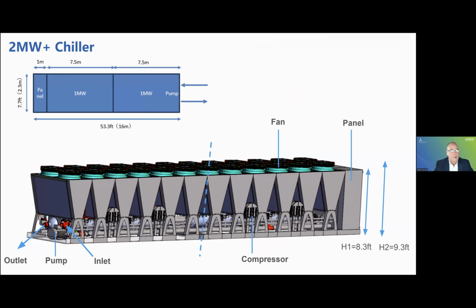Here's a look at the footprint of our 2 megawatt chiller. As you can see, as I mentioned, it's 53 feet in length, 4 compressors, 2 pumps, 7.5 feet wide by 9.3 feet high with the fans, a little bit smaller without the fans. We've designed this specifically so we can put it on a 53-foot long truck, which means a couple of things. You don't need a special route, or escort services to get the unit to the site. And secondly, once it's on site, the rigging of it is a lot easier with one solid piece being put in place, which means fewer connections for the mechanical contractors.